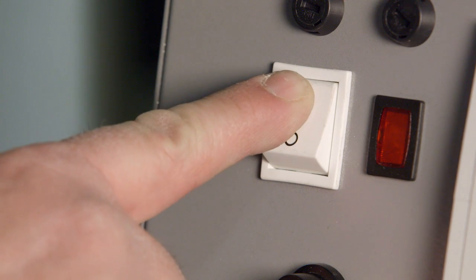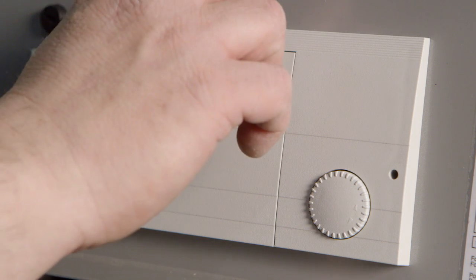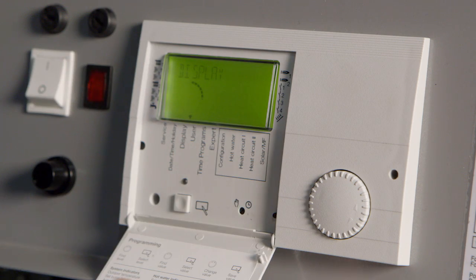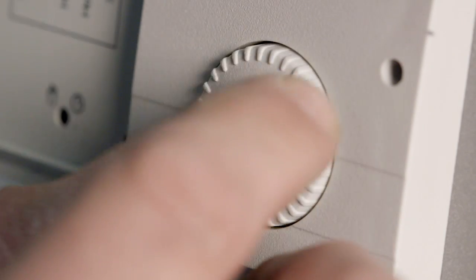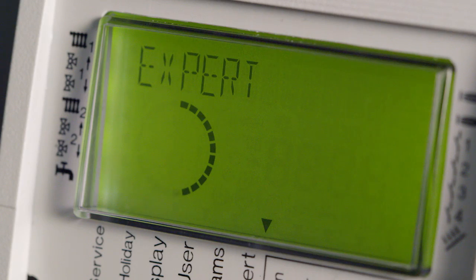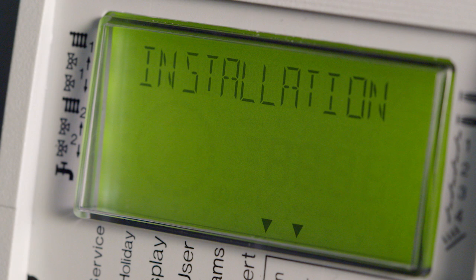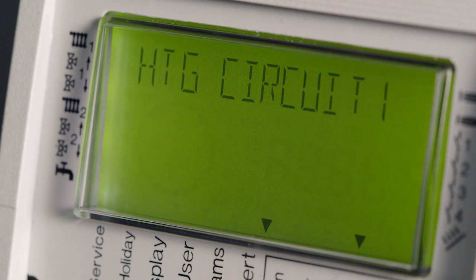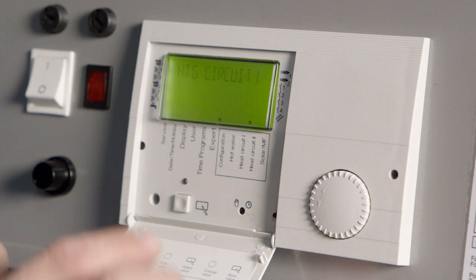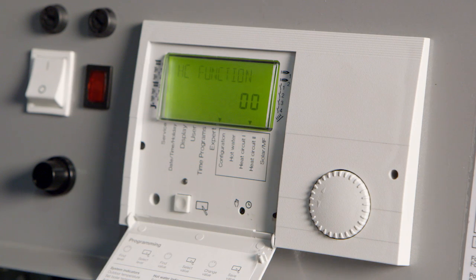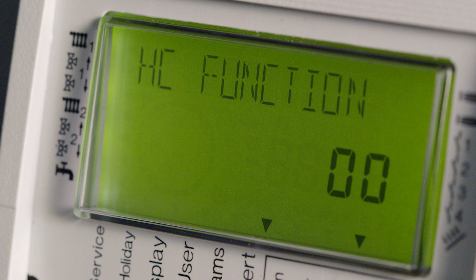Start by setting the on-off switch to on, and then open the controller's front panel. Turn the rotary knob clockwise to find the expert menu. The submenu Installation will appear. Turn the rotary knob clockwise until Heat Circuit 1 appears. Press the program key to enter the Heat Circuit 1 submenu now. This is where you'll find the unit's current setting.